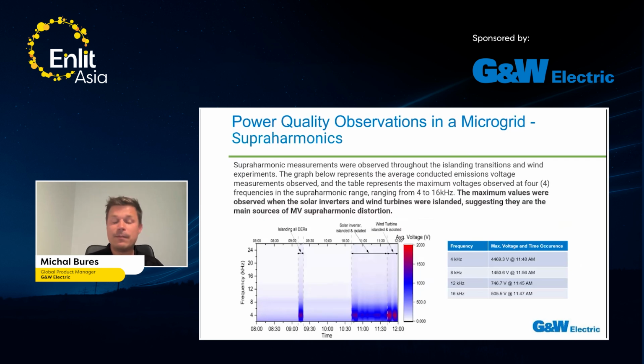Finally, another phenomenon is the supraharmonics. As you can see on the chart, we observe them again during the DERs' manipulation. The maximum values were observed when the solar inverters and wind turbines were islanded, suggesting they are the main source of the medium voltage supraharmonic distortion. In the table, you can see the maximum values that we measured with our AcuSense. For example, at 4 kilohertz it was 4,000 volts, and at 16 kilohertz we measured 500 volts.